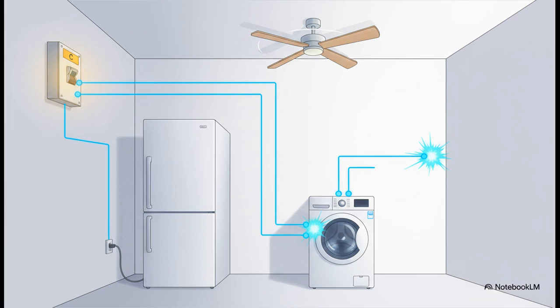Next, we have Type C. This is probably the most common breaker you'll find in a home. It's the all-arounder, specifically designed to handle that moderate inrush current you get from things with small motors, like your ceiling fan, your fridge, or your washing machine. Those motors need an extra jolt of power to start spinning, and a Type C breaker is built to ignore that normal startup surge, but still trip if a real problem happens.